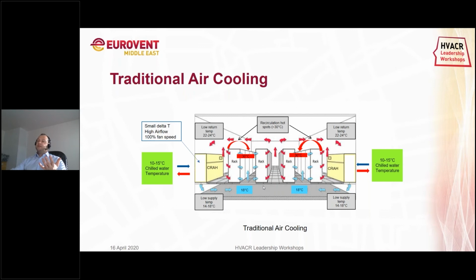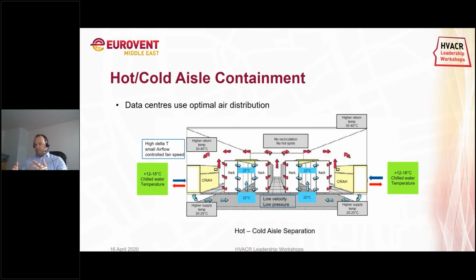The next step was hot and cold aisle containment. In this case, there was a more uniform cold temperature available at the server inlet, and there was no recirculation of the hot air and the cold air. So there was no mixture of these different air streams. The result was that a higher supply temperature was possible, and also a higher return temperature. So the chilled water temperatures were able to increase. This was the first step, and it was very important that there was a management of the air distribution.